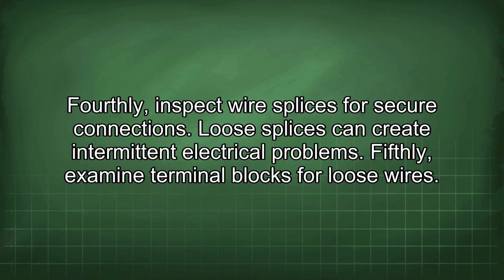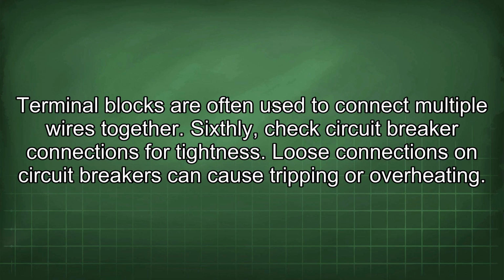Fourthly, inspect wire splices for secure connections. Loose splices can create intermittent electrical problems. Fifthly, examine terminal blocks for loose wires. Terminal blocks are often used to connect multiple wires together. Sixthly, check circuit breaker connections for tightness. Loose connections on circuit breakers can cause tripping or overheating.